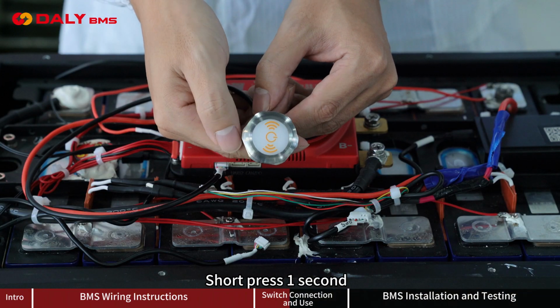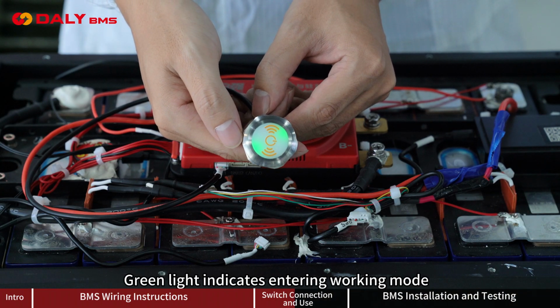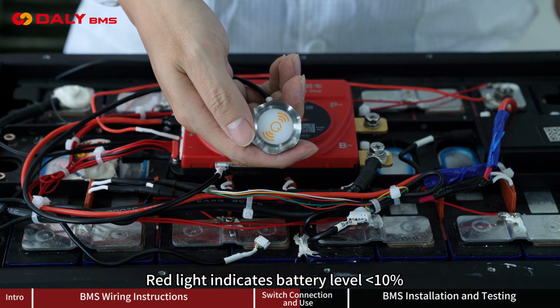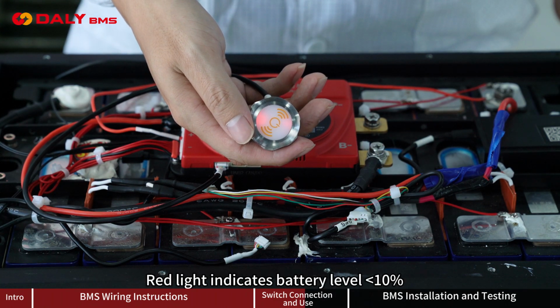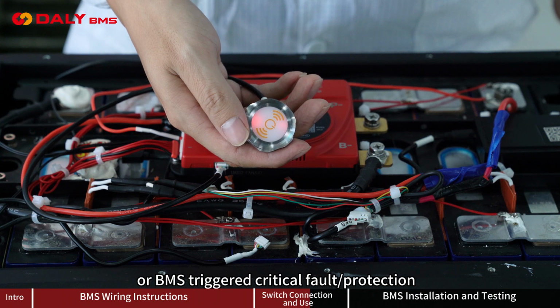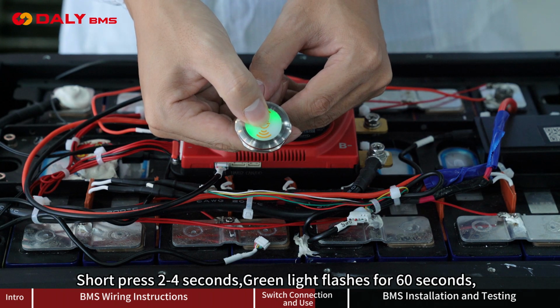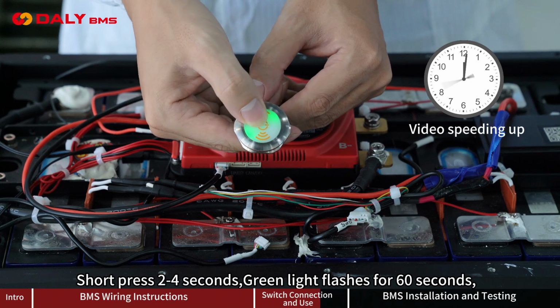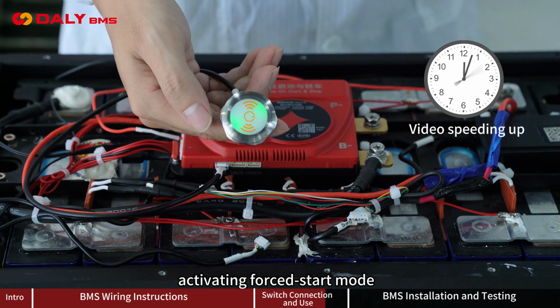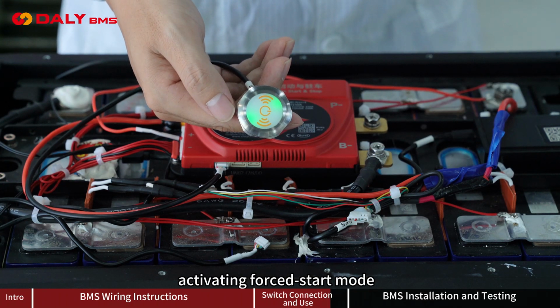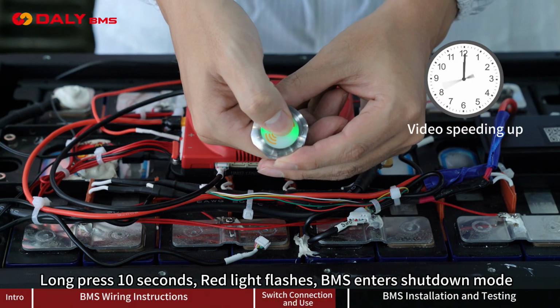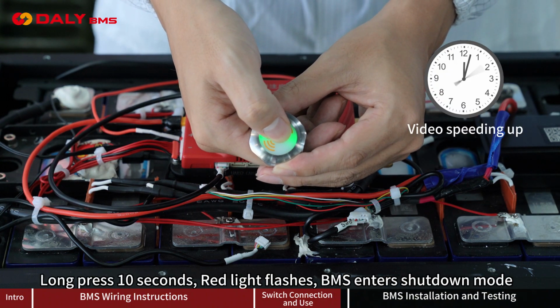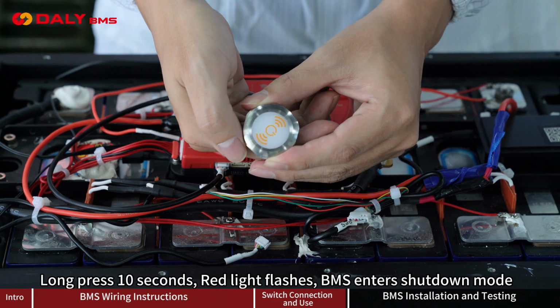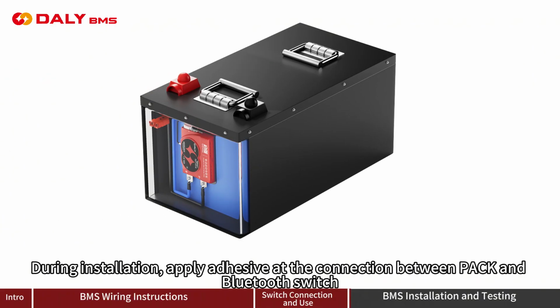Short press 1 second: green light indicates entering working mode. Red light indicates battery level less than 10% or BMS triggers critical fault or protection. Short press 2 to 4 seconds: green light flashes for 60 seconds, activating forced-start mode. Long press 10 seconds: red light flashes and BMS enters shutdown mode. During installation, apply adhesive to the connection between PACK and Bluetooth switch.